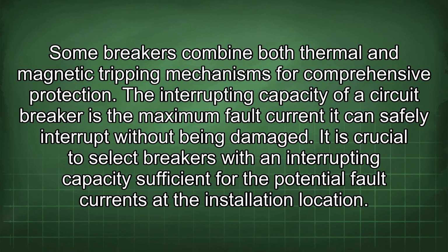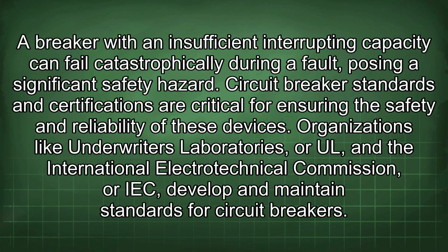The interrupting capacity of a circuit breaker is the maximum fault current it can safely interrupt without being damaged. It is crucial to select breakers with an interrupting capacity sufficient for the potential fault currents at the installation location. A breaker with an insufficient interrupting capacity can fail catastrophically during a fault, posing a significant safety hazard. Circuit breaker standards and certifications are critical for ensuring the safety and reliability of these devices.